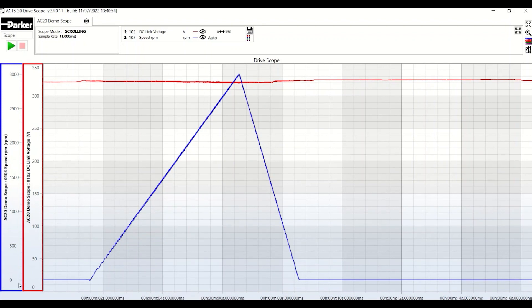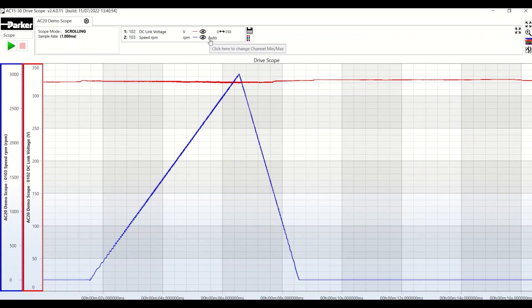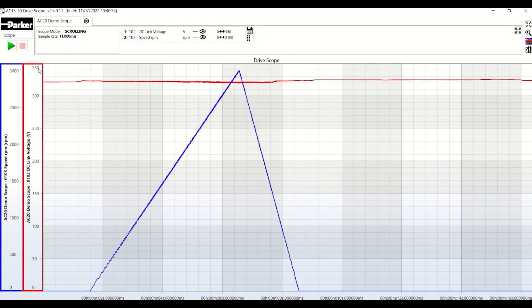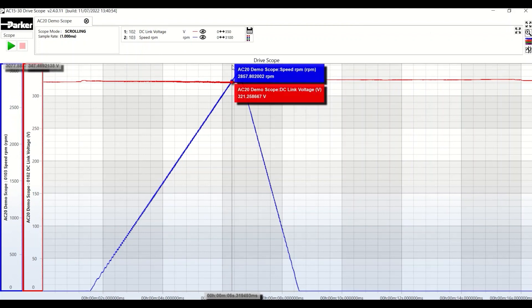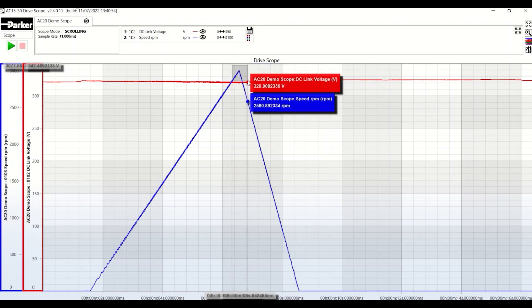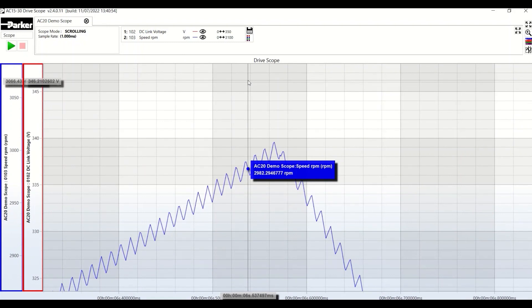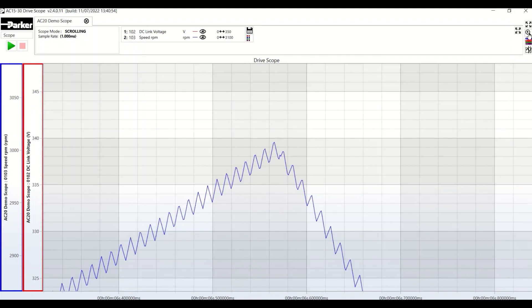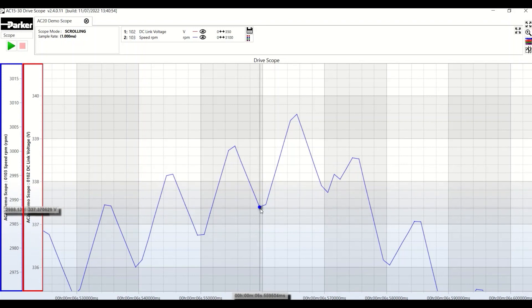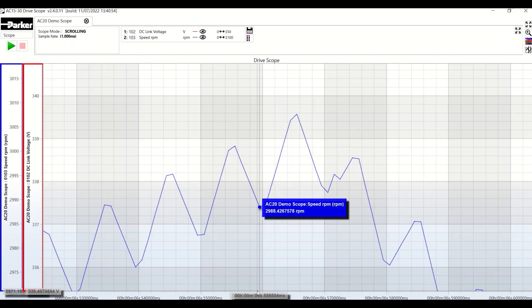Better would be to set the values between 0 and 350 volts, and then we have something more useful, with a bus voltage which varies a little but to a more reduced extent. As far as the motor speed is concerned, the value ranges from 0 to 3000, and the auto scale function is quite practical. We can also set this manually between 0 and 3100, since the maximum motor speed is 3000. To adjust the scaling, we can use the icons here — for example, the zoom icon, which allows you to zoom in on a particular section of the graph by clicking in the top left and dragging to the bottom right to form a rectangle.